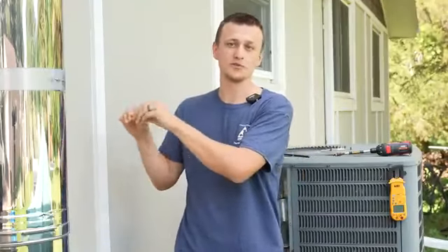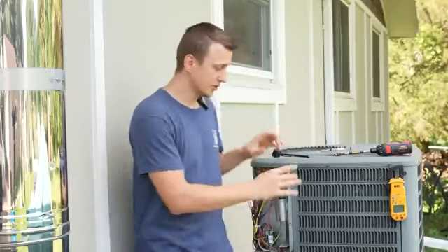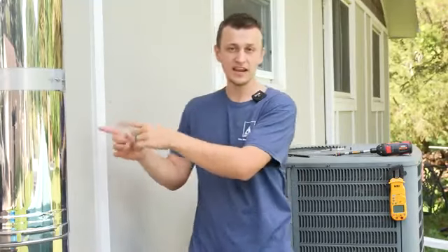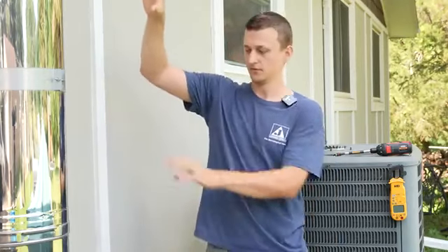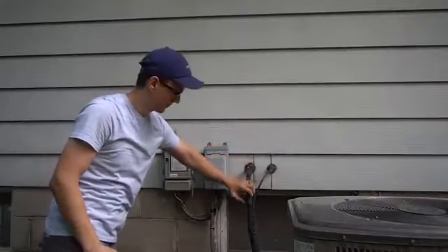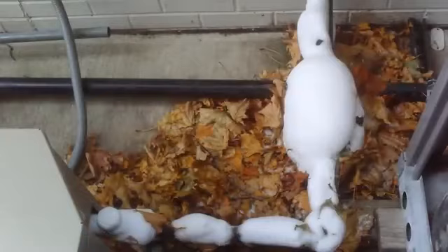Or you can have a situation where the control board does not send power to the fan motor inside. So this unit will be running just fine, but the fan inside is not getting any power. And what happens then is everything freezes up. The A coil on top of the furnace there will freeze up first, and sometimes it could turn into just a solid block of ice. But by the way, if your unit is freezing, it's not necessarily because of a bad control board. I have a video where I talk about 8 reasons why it can freeze. So before you jump to any conclusions like that, make sure you check that video out.